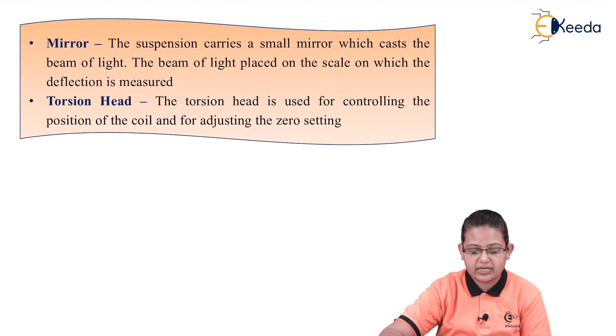Then there is a torsion head. What is the use of the torsion head? It is used for controlling the position of the coil and for adjusting the zero setting. Now why do we need to control the position of the coil? Because for accurate measurement, for greater accuracy, we need to control the position of the coil and adjust the zero setting.